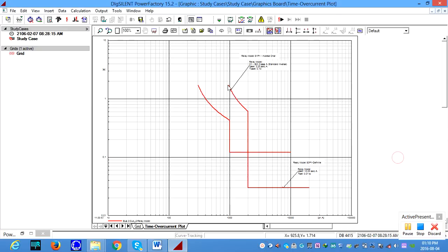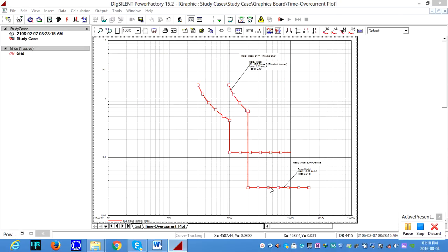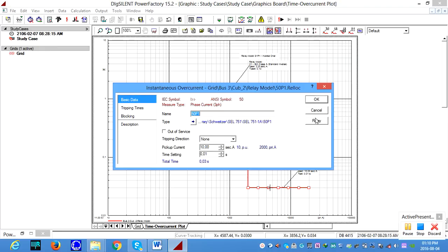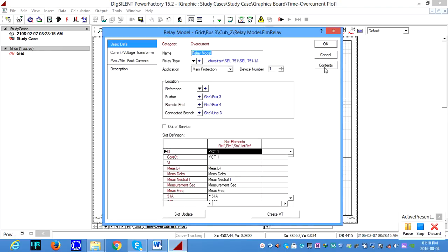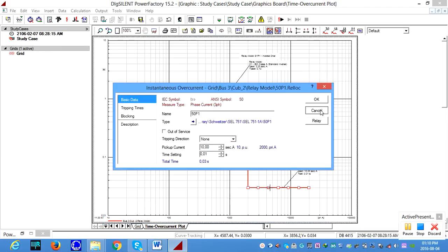So we can see for the phase element 51P1, I see inverse characteristics. And from this point onwards, you're getting a definite characteristic, that is the relay model's definite characteristic. If you want to edit the characteristics, you just click here and go to the settings. If you want to go to the relay settings, we can also go there from here.